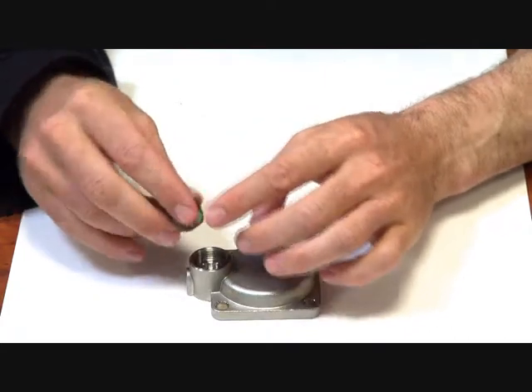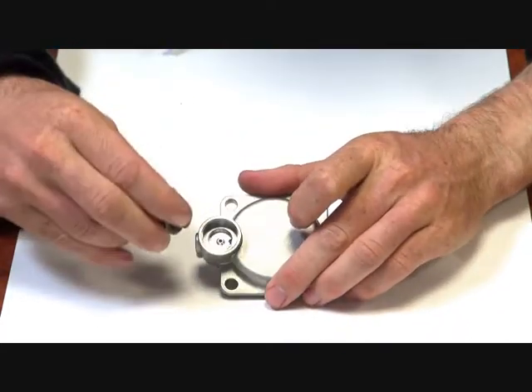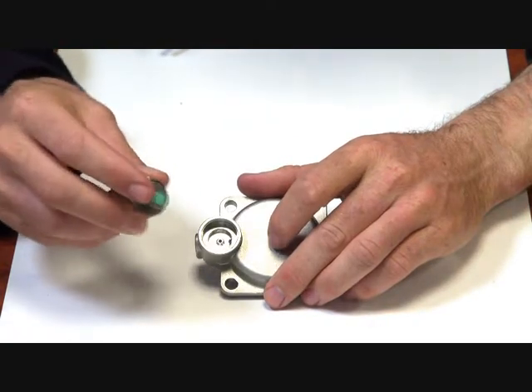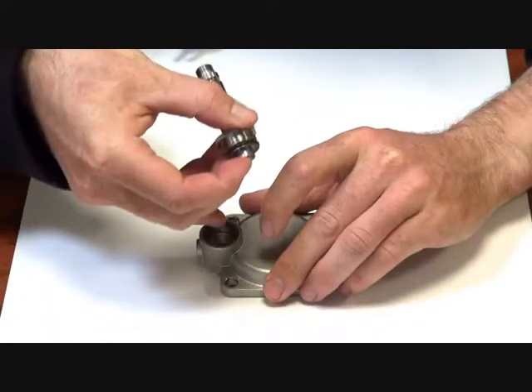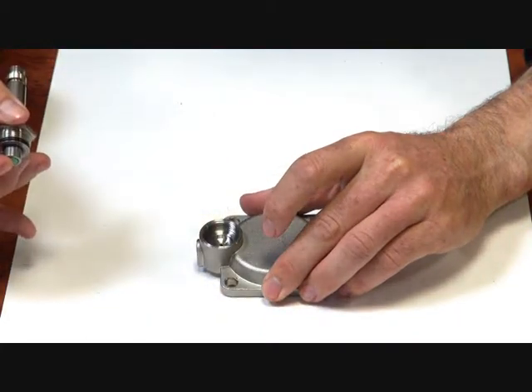Now this armature here, sits on the little jet in there. Now that sits closed. When you put power to it, just lift it up, lifts off that jet, and pressure can bleed off the top of the diaphragm.